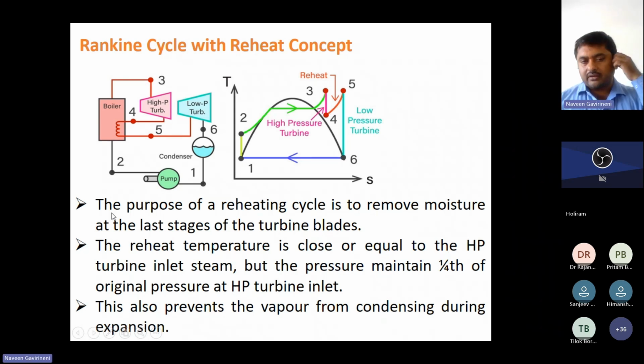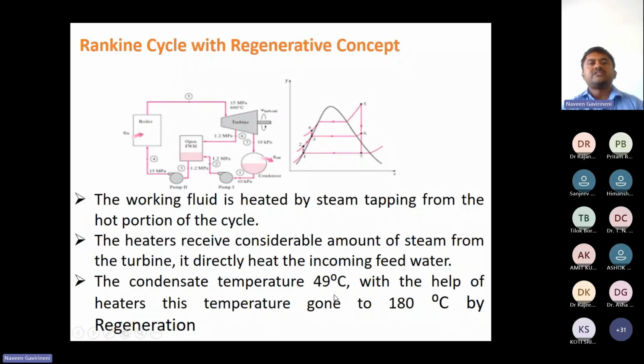So I have explained, the reheat temperature is close to the HP turbine inlet temperature. Pressure is 1/4. That means we are giving 140 kg pressure at 150 megawatt, and we are getting 37 kg at the HP turbine outlet. Again, it will go to the IP turbine at 37 kg and 540 degrees temperature. So this is the reheat concept. The second concept is regeneration.